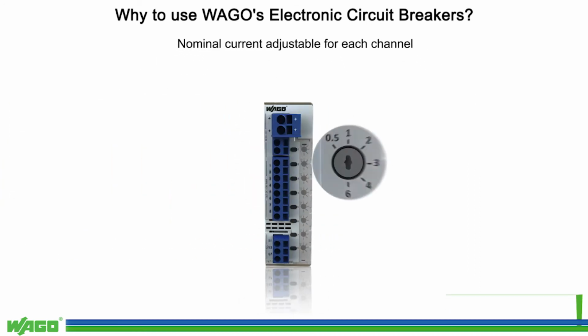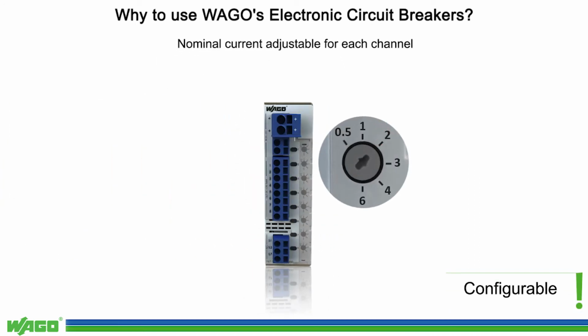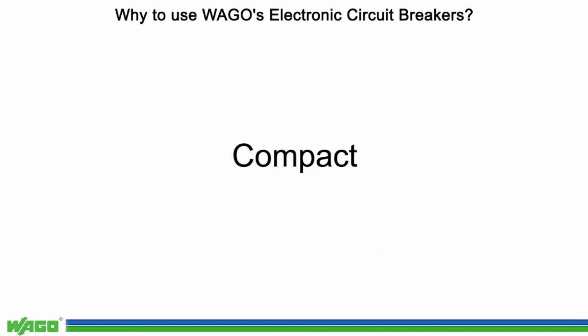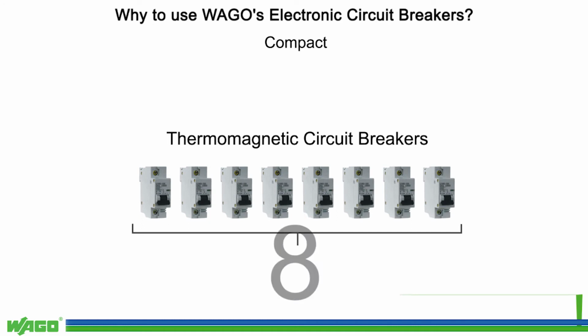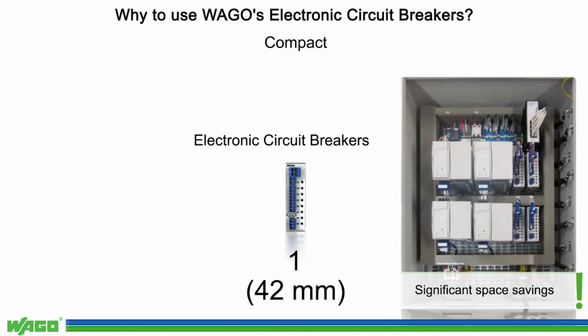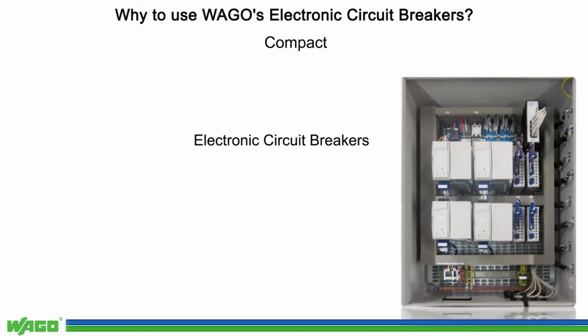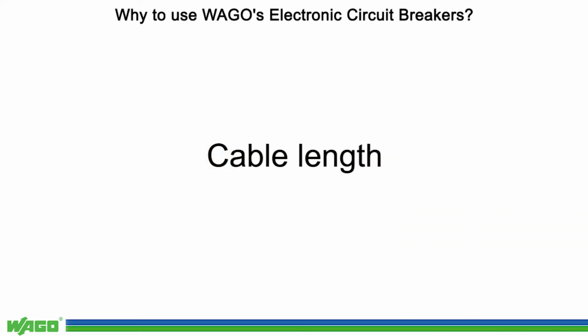Unlike thermomagnetic circuit breakers, ECBs are configurable. Both the nominal current and related trip curve can be set separately for each channel. ECBs also require significantly less space. As this example shows, an ECB may replace up to 8 thermomagnetic circuit breakers. The space required is therefore reduced from 140 to 42 millimeters in width. This space savings means that control cabinets can be even more compact.